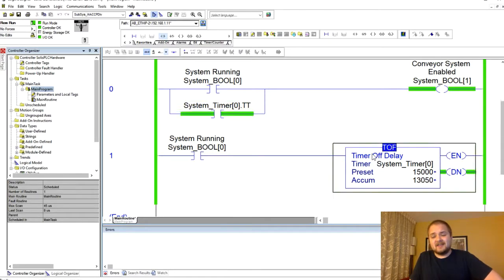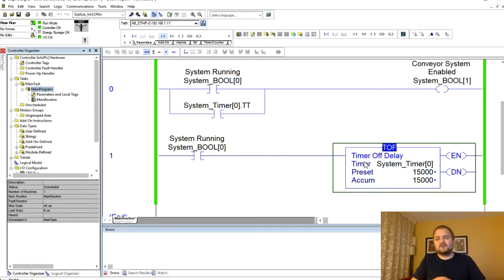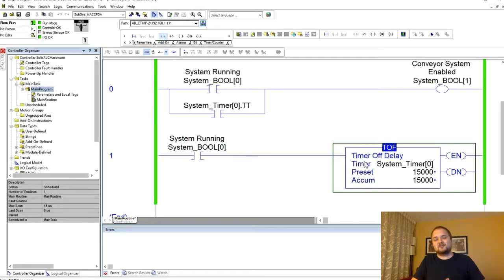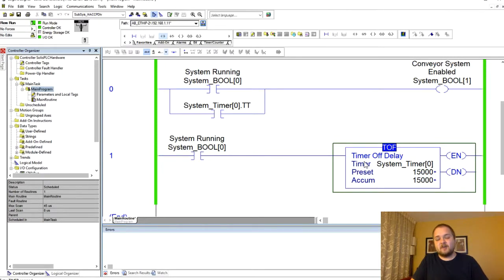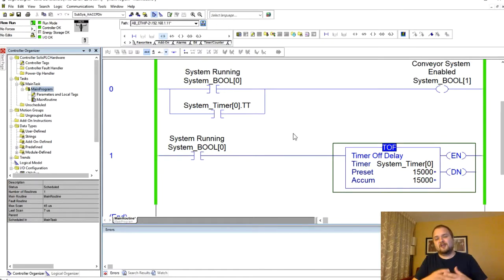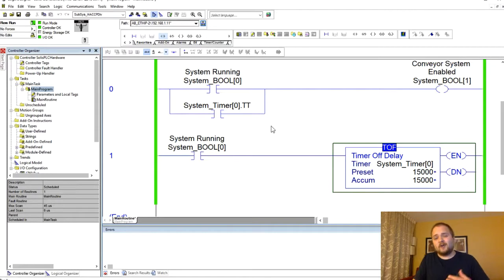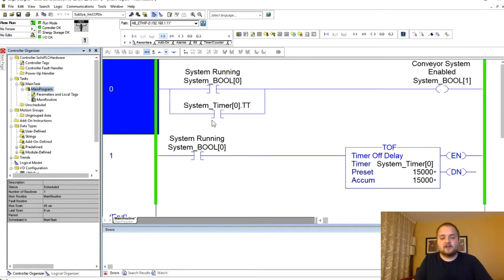Now I've seen this timer off delay function or instruction being used in many different locations where a TON should be used. Always use a consistent scheme for your instructions and only use timer off delay if it's absolutely impossible to do that with a timer on delay or it is just more convenient to use a timer off delay.